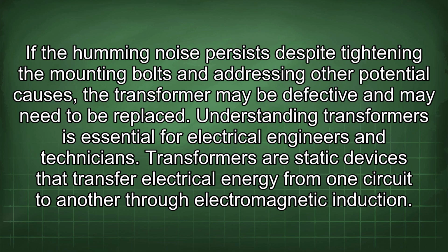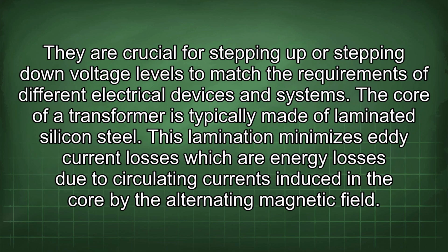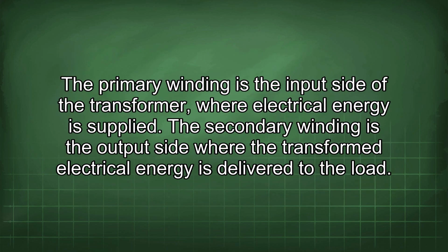Understanding transformers is essential for electrical engineers and technicians. Transformers are static devices that transfer electrical energy from one circuit to another through electromagnetic induction. They are crucial for stepping up or stepping down voltage levels to match the requirements of different electrical devices and systems. The core of a transformer is typically made of laminated silicon steel. This lamination minimizes eddy current losses, which are energy losses due to circulating currents induced in the core by the alternating magnetic field. The primary winding is the input side of the transformer, where electrical energy is supplied.